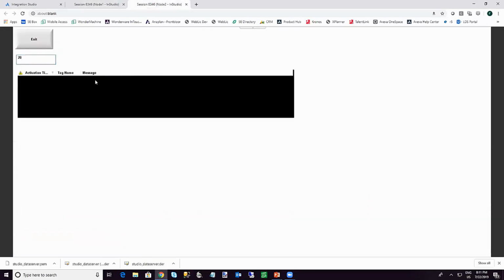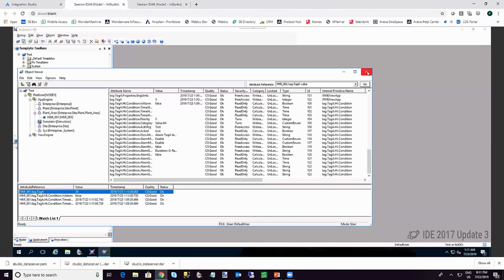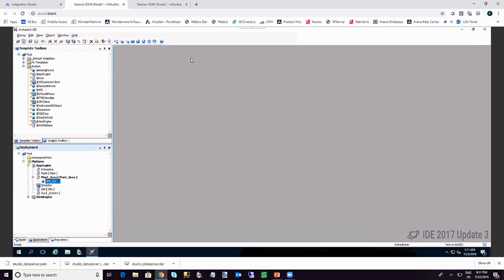I just enabled the security system now, which is strongly recommended. So System Platform uses the authentication, a particular username and password to connect to InTouch Edge HMI, and then InTouch Edge HMI trusts this connection to exchange tag values and alarm status. One last configuration that's possible, and I'll demonstrate here, is encryption. Also, to increase the security in the communication between InTouch Edge HMI stations and System Platform, you can enable encryption as well using TLS between InTouch Edge HMI and System Platform.